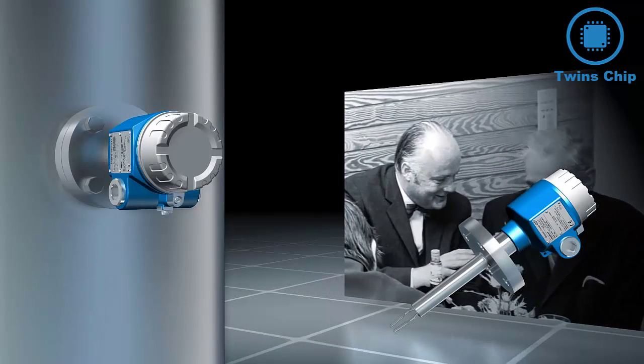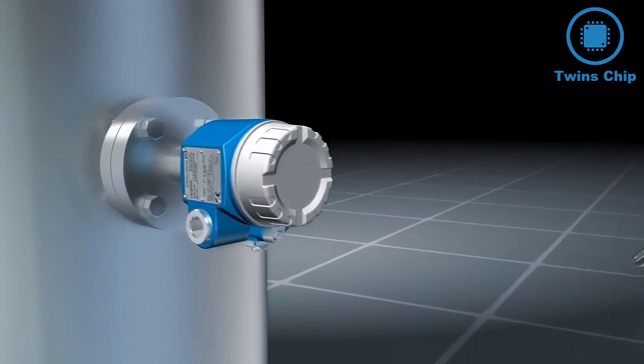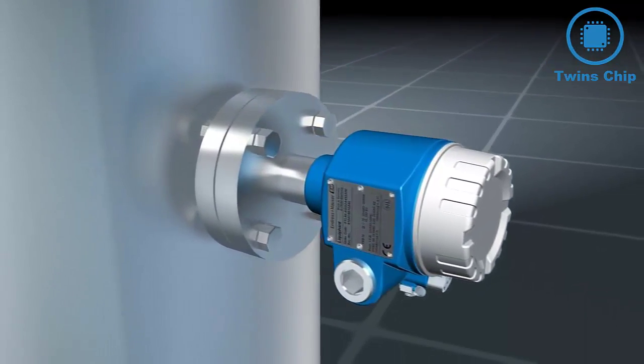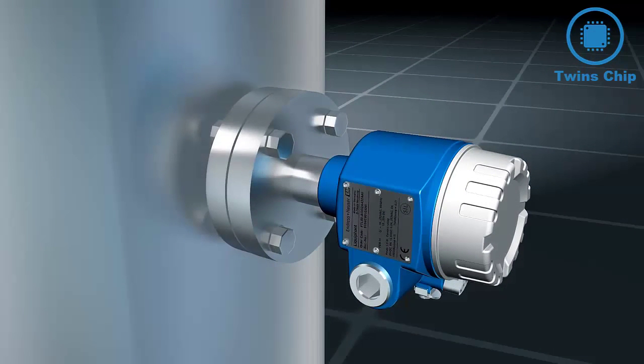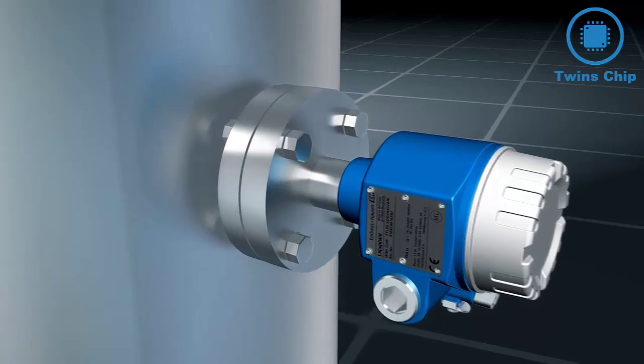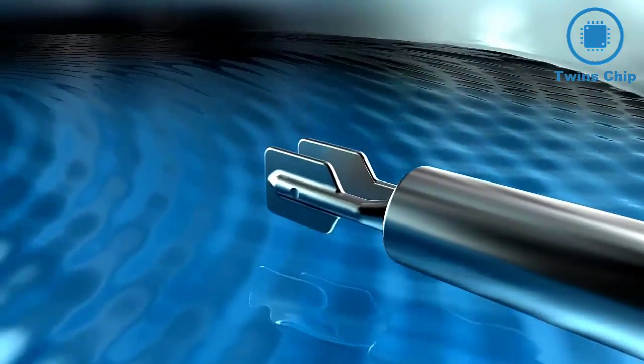This principle uses the direct correlation between oscillation and damping in media. Let's have a closer look at how this measuring method works. Vibronic instruments monitor point levels in tanks, containers and pipes. A sensor in form of a tuning fork is excited to its resonance frequency.